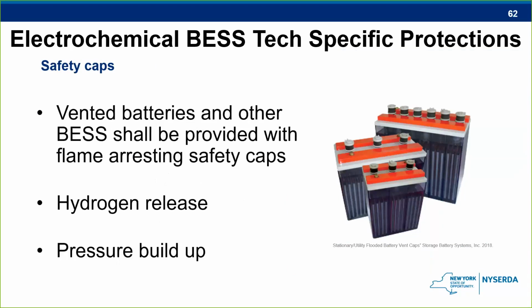Some battery types will also require safety caps. For example, hydrogen is a byproduct of the lead-acid battery charging and discharging process. So in addition to ventilation, safety caps are designed to open and release any gas buildup without allowing flames to enter the battery.